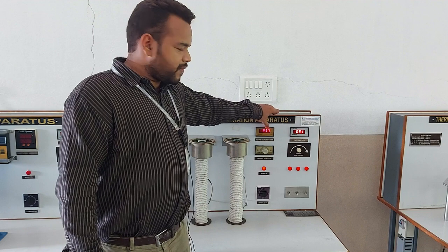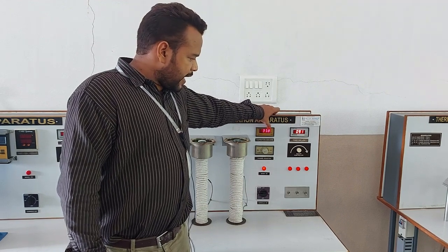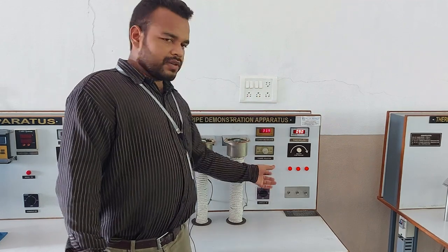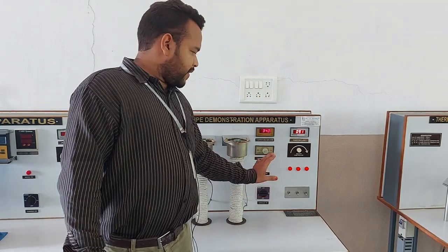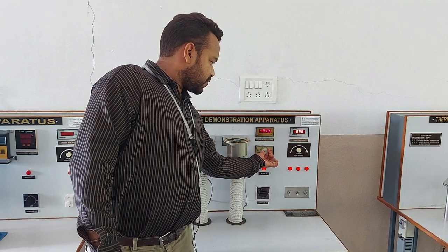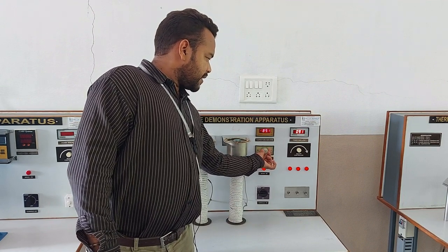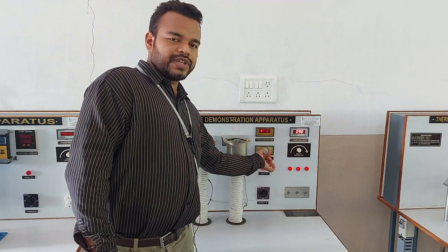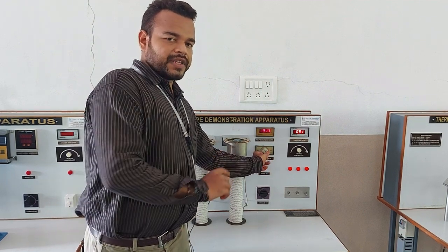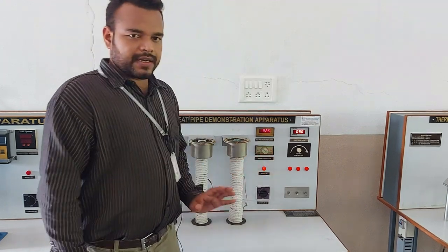Earlier it was 33.5 something, now it is 6, 7 and then 8, it will rise until it becomes steady. So, we need to wait for a while, and once it reaches the steady point, just regulate this to channel 2, channel 3, channel 4, channel 5, channel 6, so that we can get the temperature readings. That will be one set.